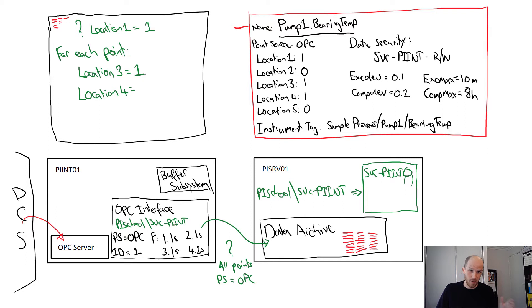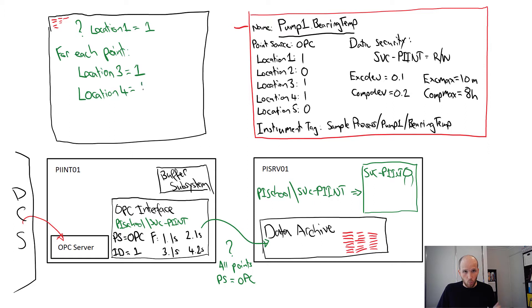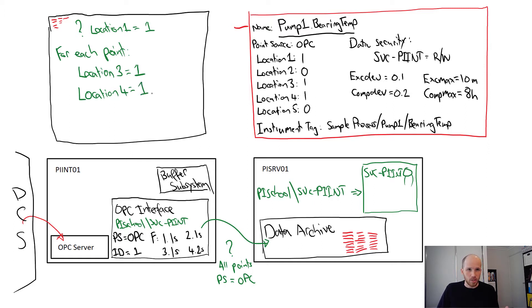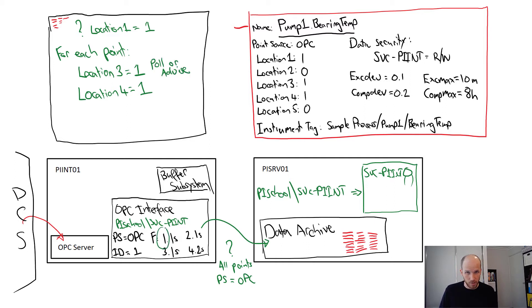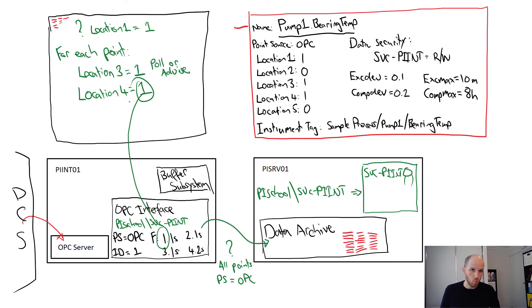Speaking of scan frequency, in the case of our bearing temp tag, it has a location 4 of 1. The interface matches this up with a list of scan frequencies. It finds the first scan frequency, because the location 4 is 1, and it sees that it's 1 second.